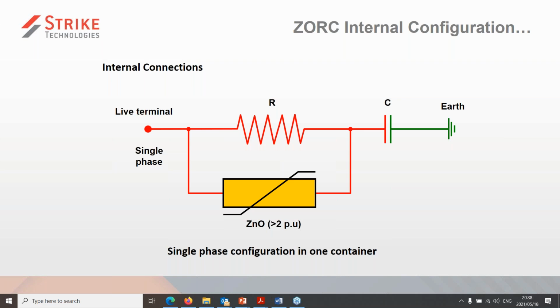In matching the surge impedance of the cable, that 30 ohm resistor prevents that surge from bouncing back effectively, in layman's terms, and therefore getting rid of the multiple pre and restrike events, getting rid of the voltage doubling concept that is associated with vacuum and some other switchgear.